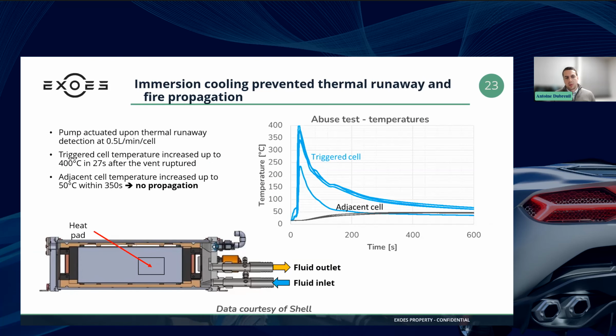So we'll now take a look at the results, and we thank Shell for allowing us to share these results with you today. You will see in this graph temperatures against time across the test. In blue, you will see the temperature measurements on the triggered cell, with different temperature profiles because we have multiple thermocouples on the cell. And in black, you see temperatures on the adjacent cell, that's the cell directly facing the triggered cell. What you can see is that very quickly, in less than 30 seconds, we reached more than 400 degrees Celsius on the triggered cell. The system automatically activated the pump and was able to maintain the adjacent cell temperature below 50 degrees Celsius in this case. So this was a very safe test outcome and effectively a successful test in that sense, which concluded with no propagation of thermal runaway.